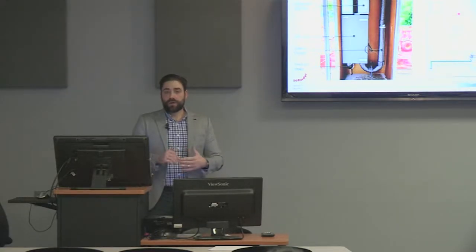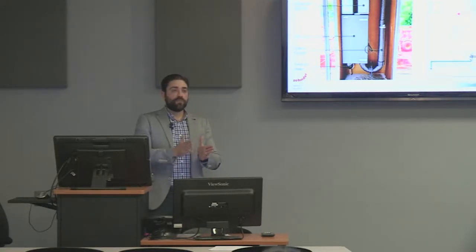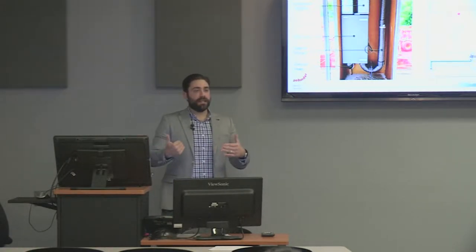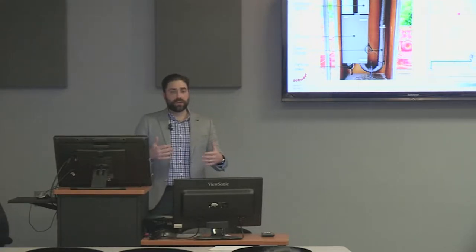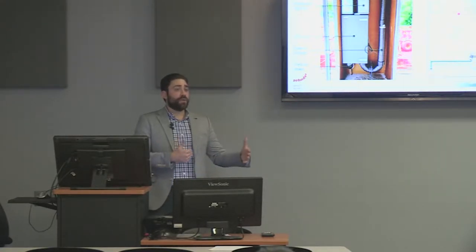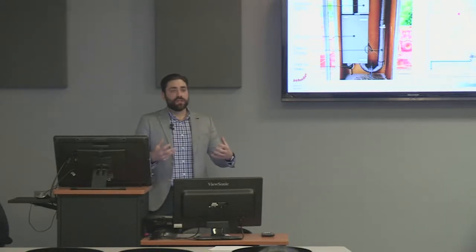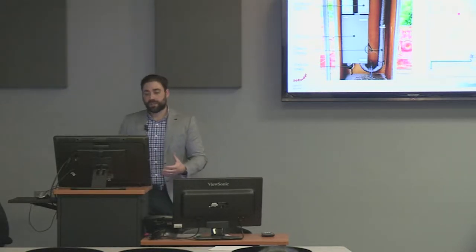These units are ERVs — enthalpy recovery ventilation units. So we're actually recovering some of the moisture during the wintertime so we don't dry out the apartments. And we're also trying to move moisture to the exterior airstream during the summertime to minimize our latent load on our mechanical system. We want to make sure that the load on the mechanical during the cooling side, where we have to remove moisture and do a lot of dehumidification, is minimized by using this unit.